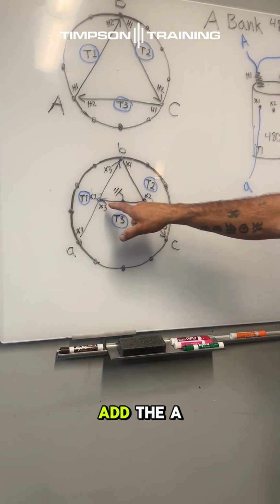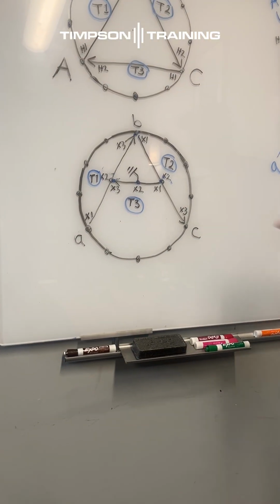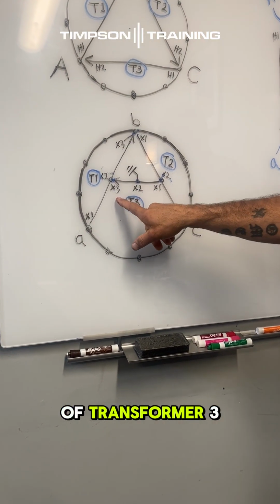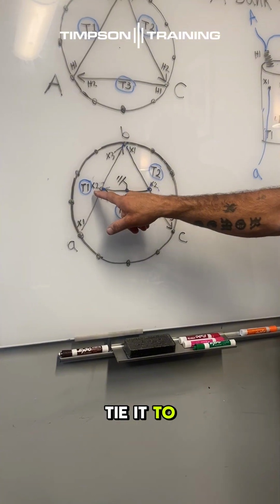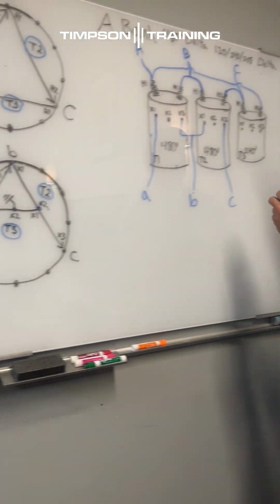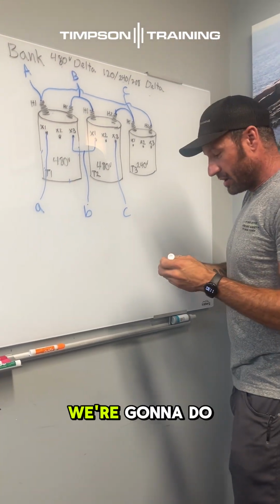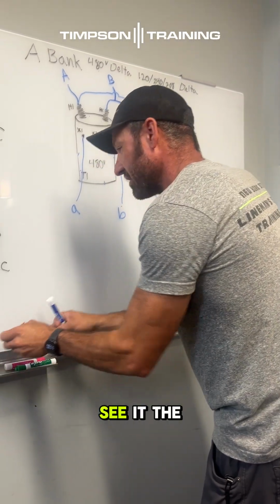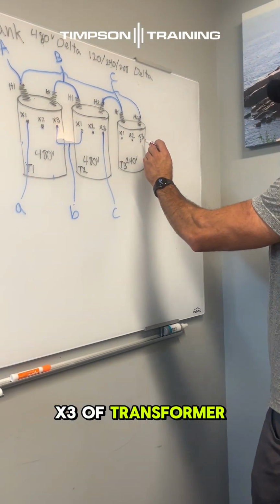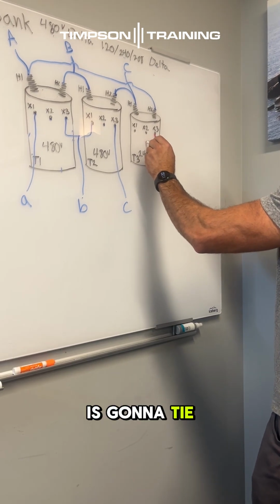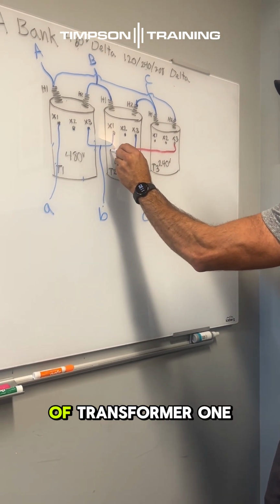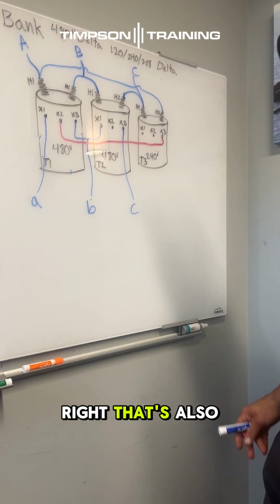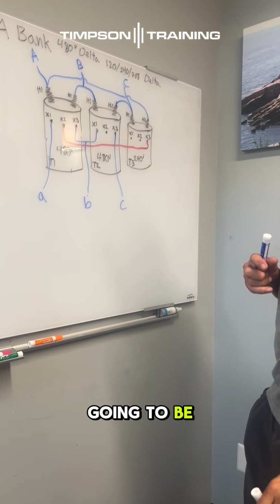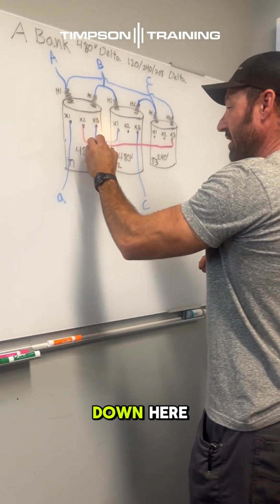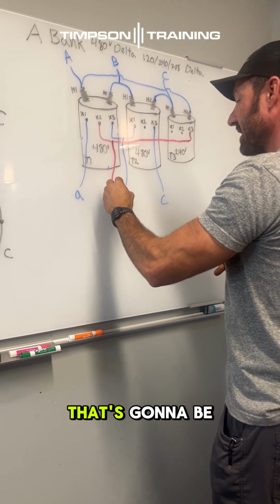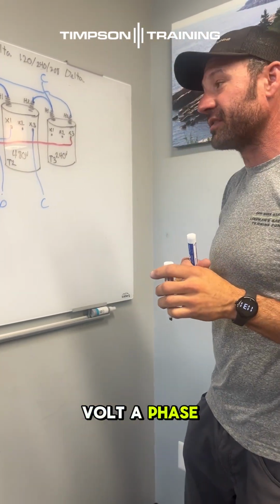Now, we're going to add the A bank in on the secondary. So we're going to take the X3 of transformer 3, and we're going to tie it to the X2 of transformer 1. Now it's going to look a little wonky. We're going to do this in a different color so you can see it. The X3 of transformer 3 is going to tie to the X2 of transformer 1, right? That's also going to be A phase. So we're going to bring a line down here and make that A phase. That's going to be your 240 volt A phase.